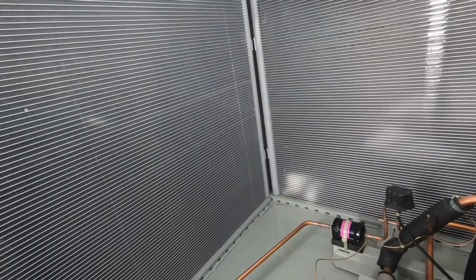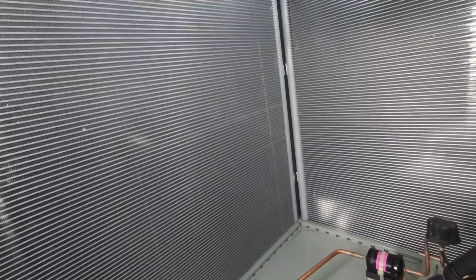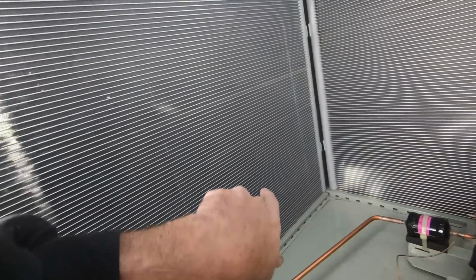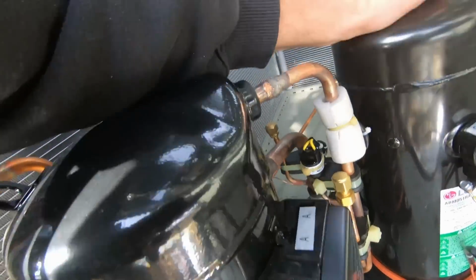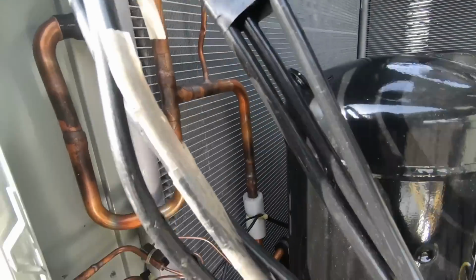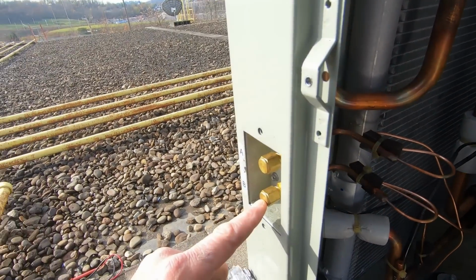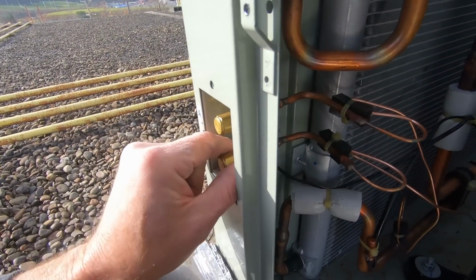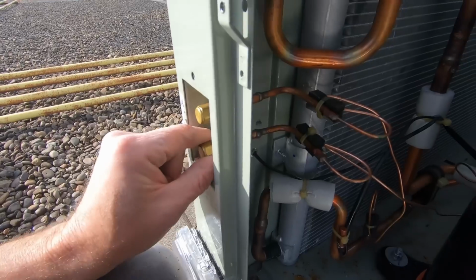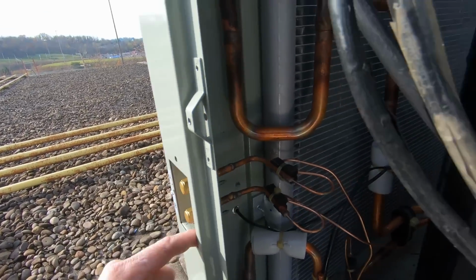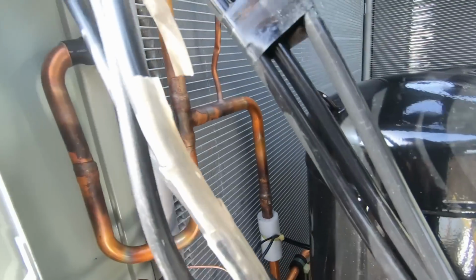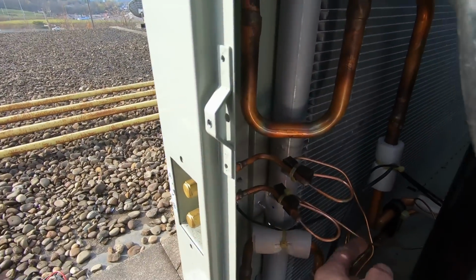2 separate condenser coils, I like. If we get a leak in the coil, you don't have to recover the refrigerant out of both circuits. Assuming that's second stage and this is first - I don't know, don't quote me on that - but I like the 2 separate condenser coils. That's nice. And you've got your suction line pressures right here, A and B. It doesn't appear that they give you a high side port. Let me make sure.